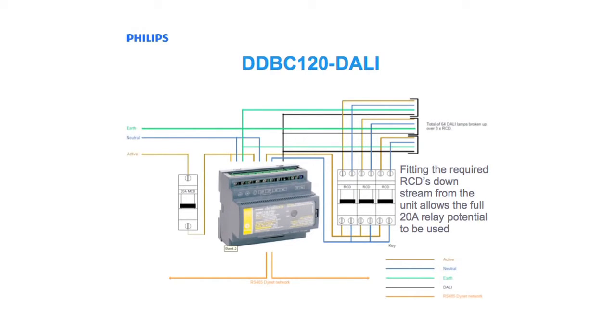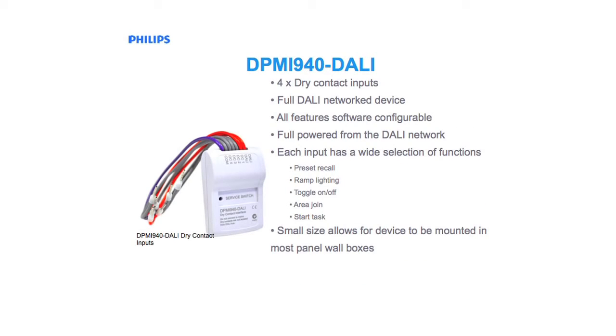The DPMI 940 DALI is a 4 dry contact input device that is fully DALI network compatible. It does not require an external power supply and connects directly to the DALI network. The unit is completely software configurable. It has no requirements for manual trim pots or DIP switches. The only input into the device is the service switch used during commissioning. Pressing this service switch allows the commissioning technician to locate the device's address.